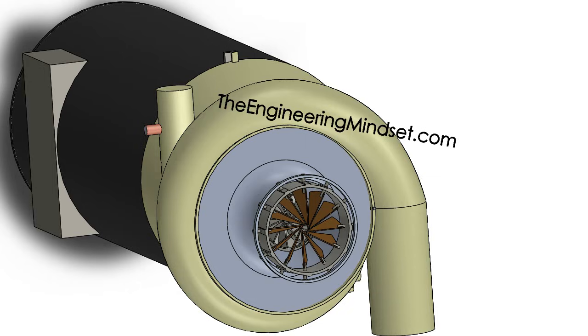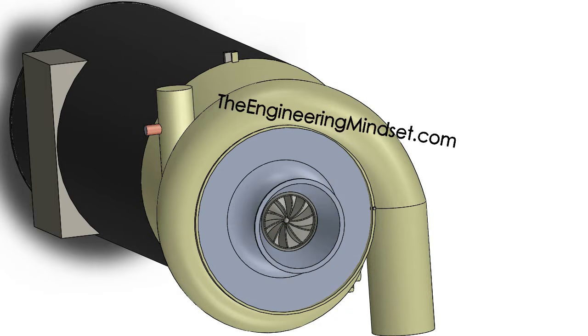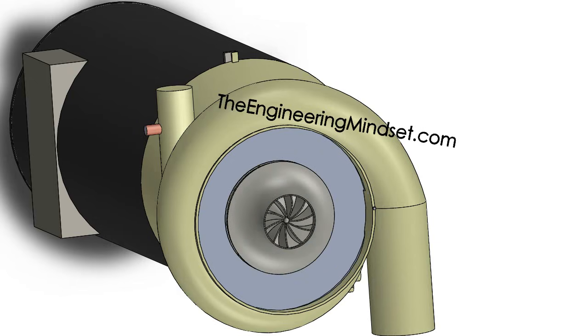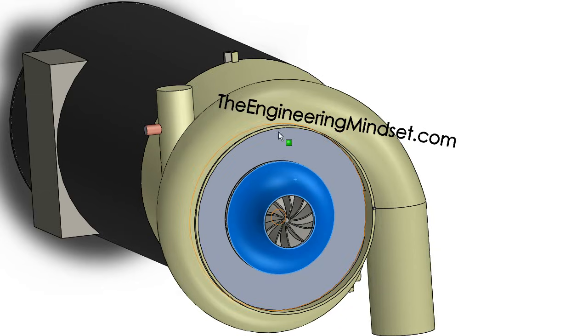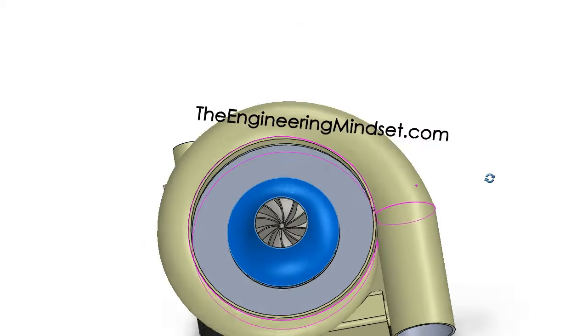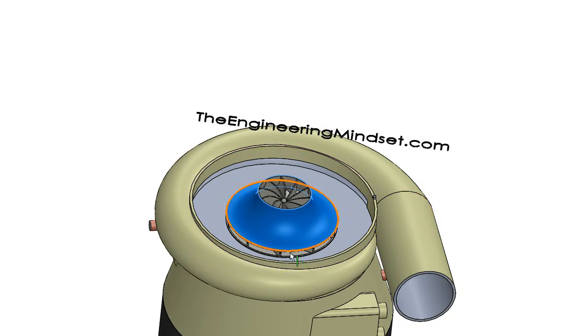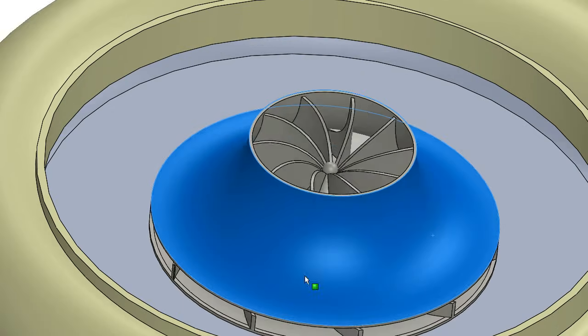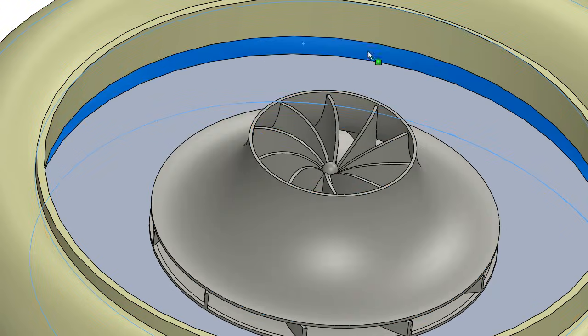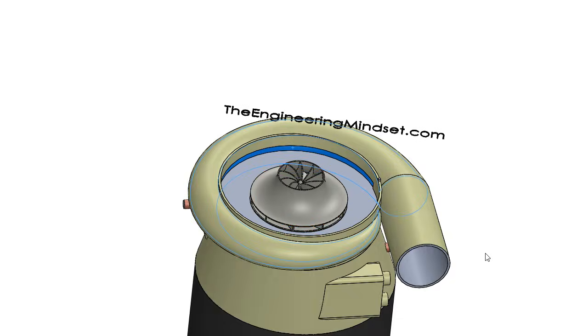So underneath the first part of the cover, we've got the vane guides there, which do the capacity control. We've got another video on that if you want to learn how the chiller capacity is controlled. And behind that we've got the inlet shell, and then we come down to the actual compression chamber, exposing the impeller here, along with the diffuser, which is just here in between the compression chamber and the volute. The volute is this area here, this spiral around the perimeter of the compression chamber, and I'll just show a different angle there so you can see a bit better. So here we've got the impeller, and this gap in between is the diffuser. Just a small gap running between the two.